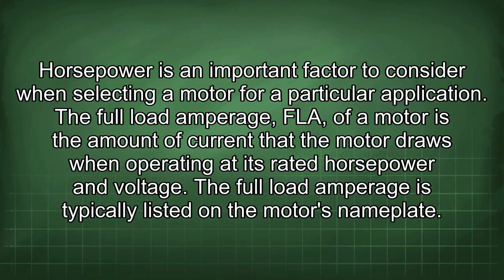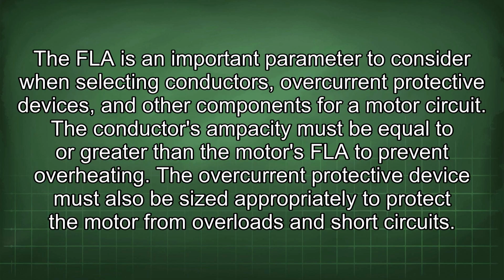The full load amperage, or FLA, of a motor is the amount of current that the motor draws when operating at its rated horsepower and voltage. The full load amperage is typically listed on the motor's nameplate. The FLA is an important parameter to consider when selecting conductors, overcurrent protective devices, and other components for a motor circuit. The conductor's ampacity must be equal to or greater than the motor's FLA to prevent overheating. The overcurrent protective device must also be sized appropriately to protect the motor from overloads and short circuits.